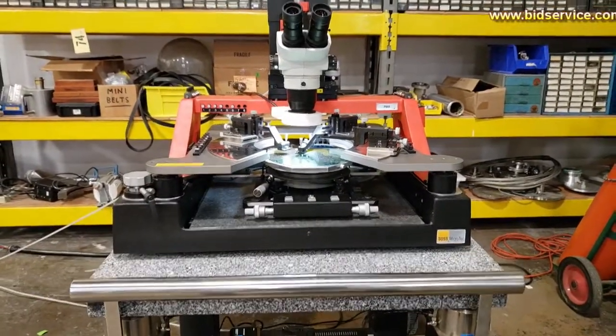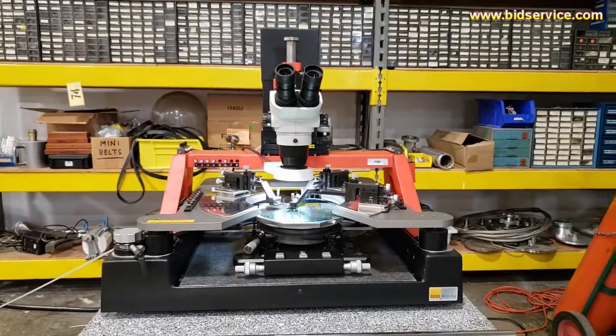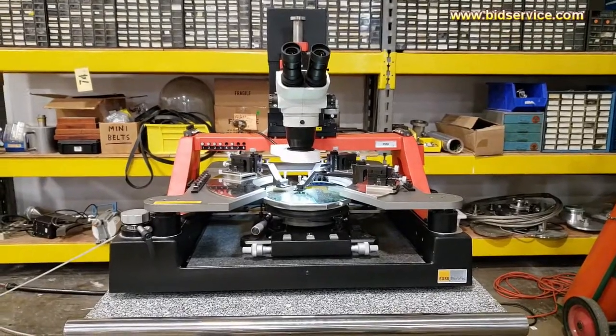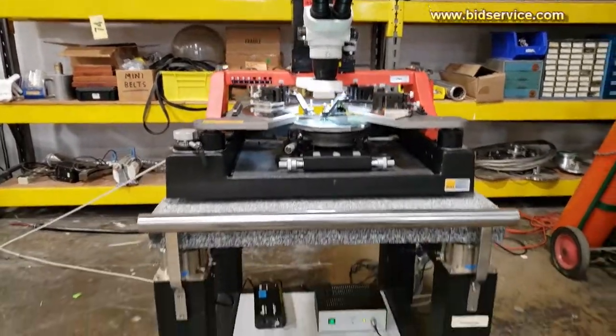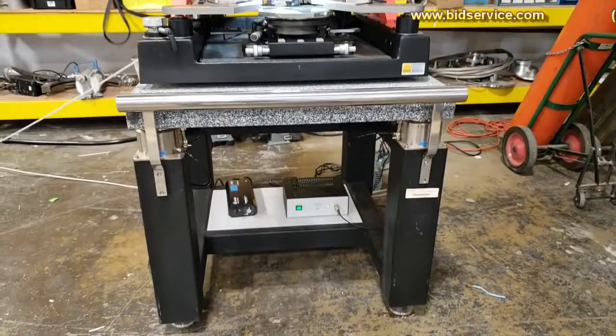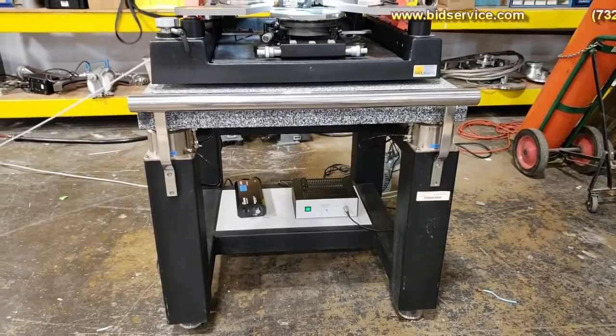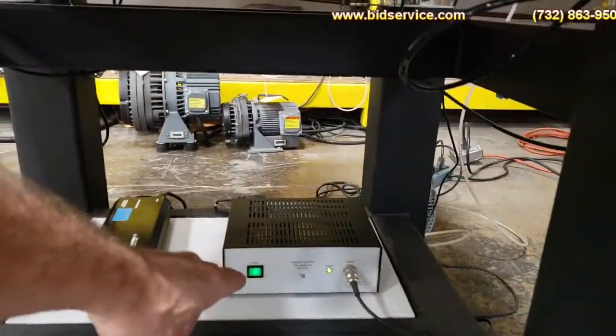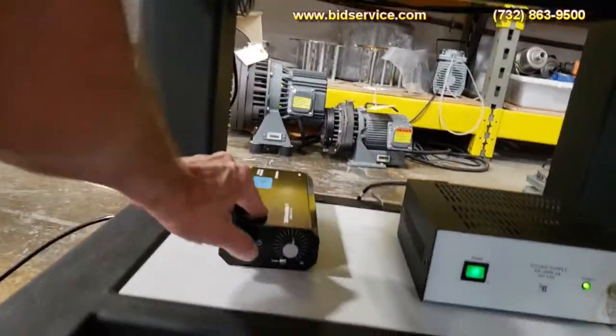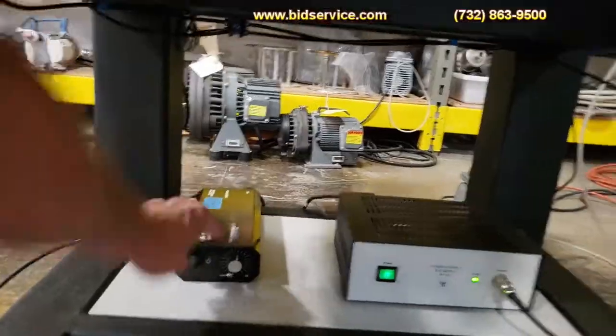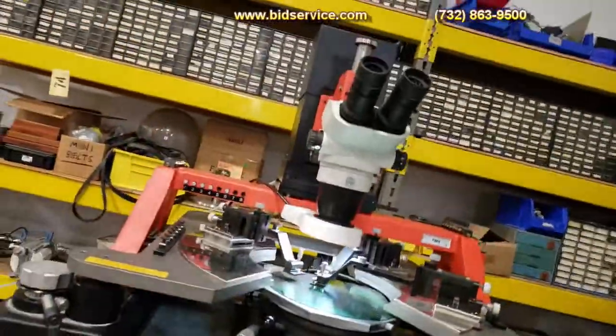Okay, this is our video demonstration of the SUSS MicroTec PM8 probe station, and it's sitting on an isolation vibration table. The only power requirements is we got 110 to our power supply and our light source power supply. So turn the light source on and off. And it's off. Press the button again and turn it on.